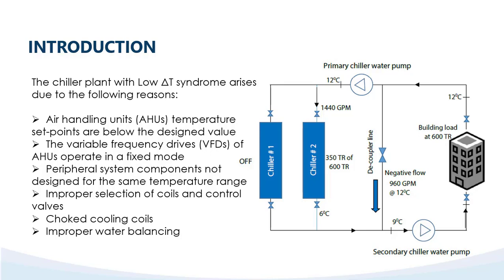What are the problems? Why is this plant behaving like this? The chiller plant with low delta T syndrome arises due to the following reasons. Point number 1: AHU temperature set points are below the designed value. Now here we want 6 degree supply, but if our AHU set point is kept at 12 or 10 degrees, it is never achieved. So we have to keep the digital thermostat at 24 plus or minus.